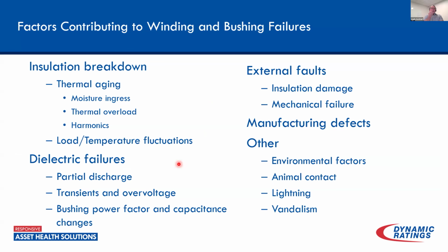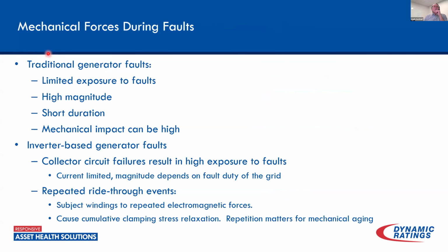So now we're talking about factors that affect insulation breakdown, dielectric failures, things like that. Mechanical faults can be a concern, especially with distribution transformers and transmission-based assets. Through faults are typically one of the leading causes of failures in those. With GSUs, as we saw in the first few slides, it's not as great of a concern. If we look at traditional generators, we have limited exposure to faults. We don't see a lot of faults with those. They tend to be high magnitude but fairly short duration, lower frequency, but they can have a significant mechanical impact. There are a lot of forces behind there. So we typically see it's more of a mechanical nature when it comes to those rotating machine-based assets.